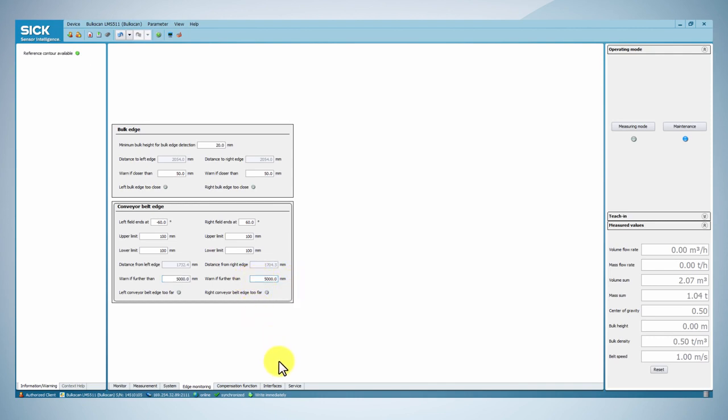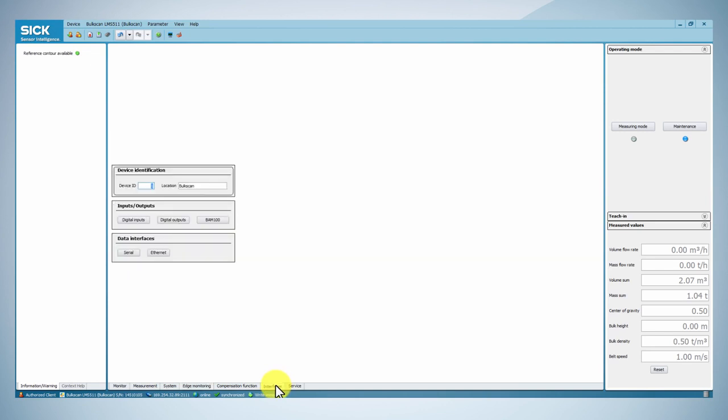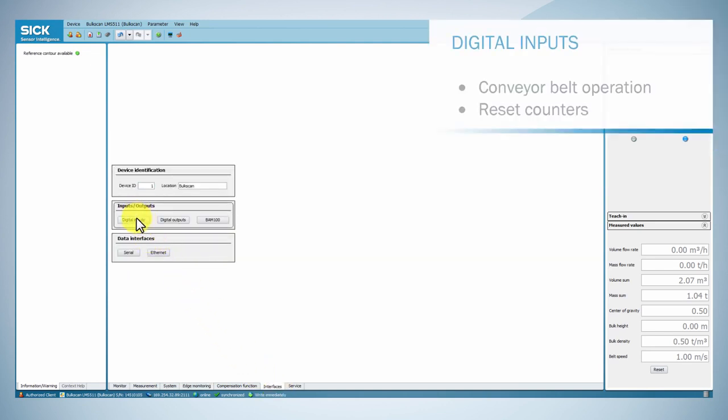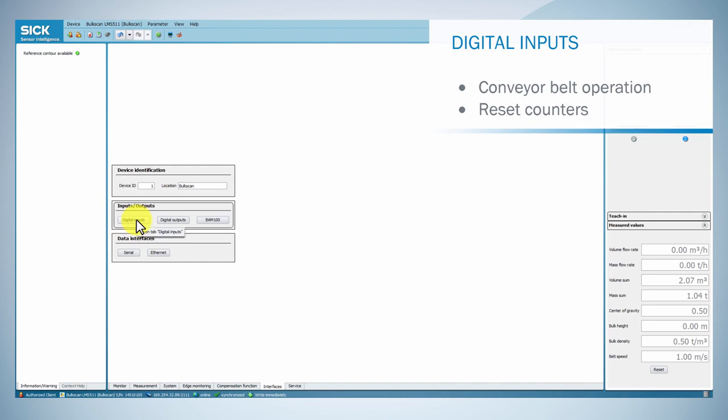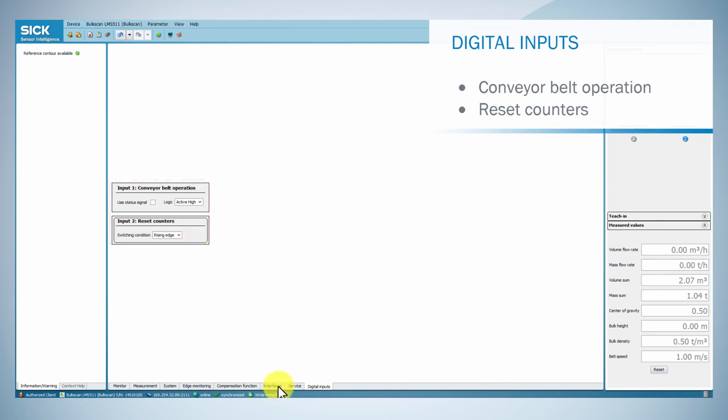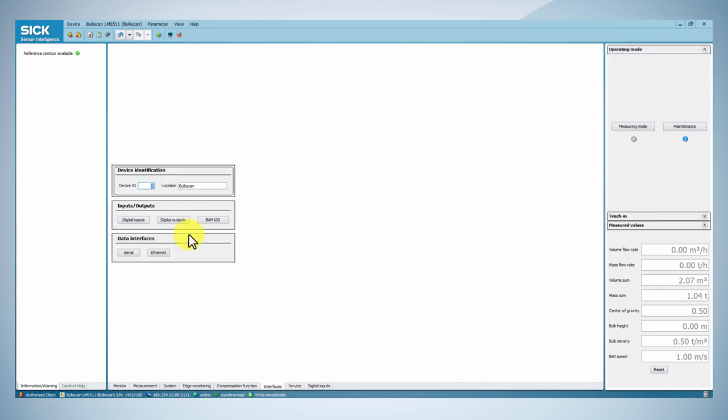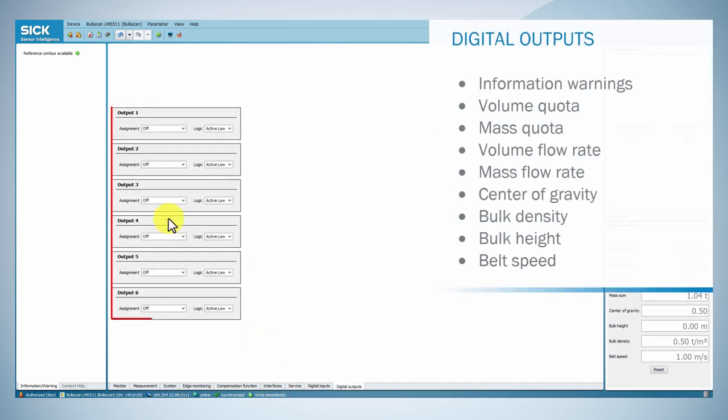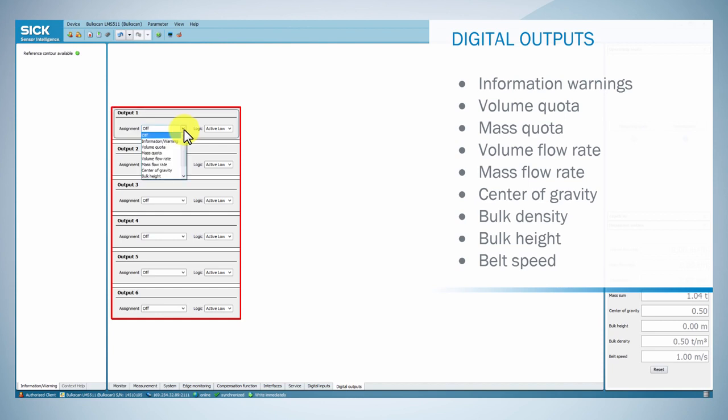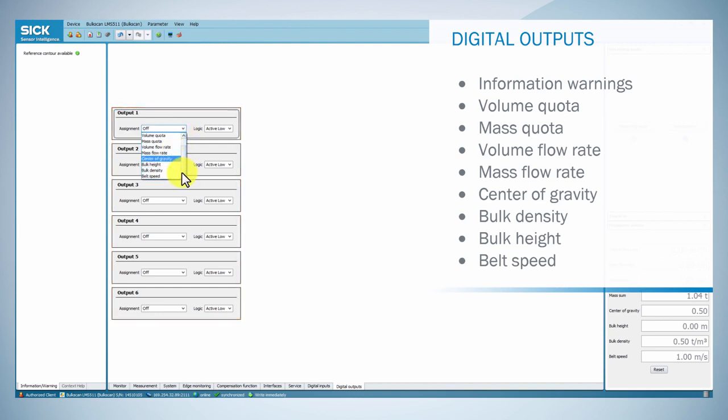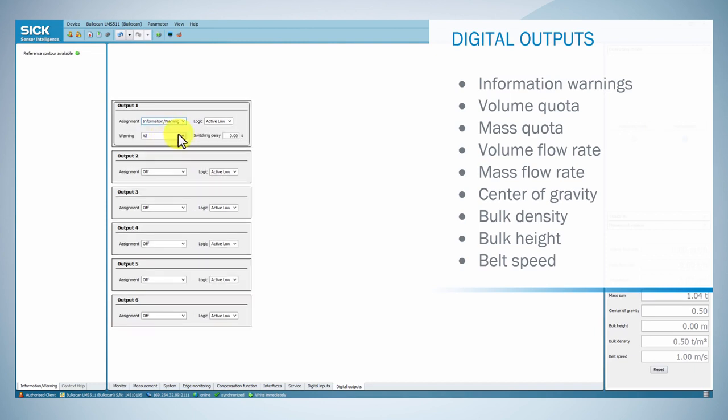The Bulkscan LMS 511 has two digital inputs which are used to signal the belt operation and reset the volume sum and mass sum. It also has six digital outputs in which the sensor can signal that certain totals have been reached, limits have been exceeded or dropped below, or the occurrence of information warnings.